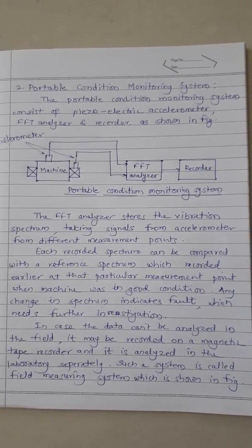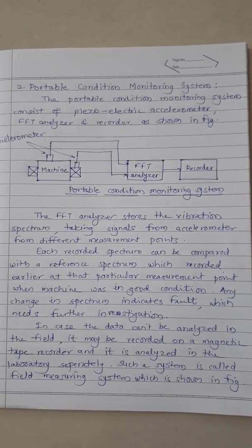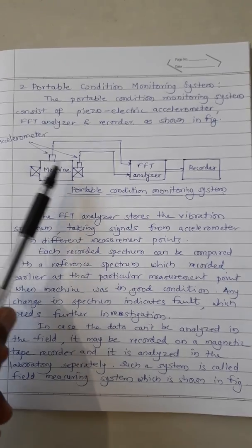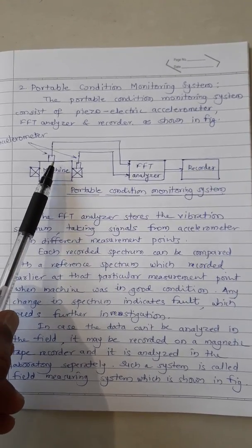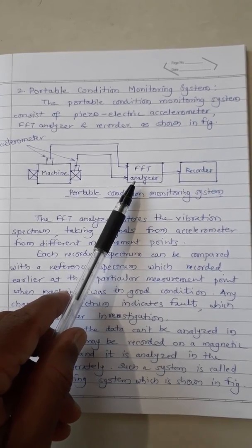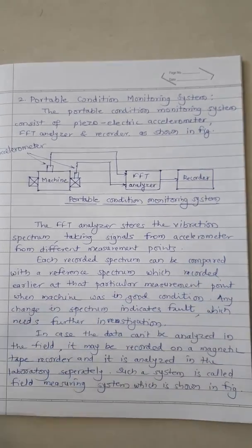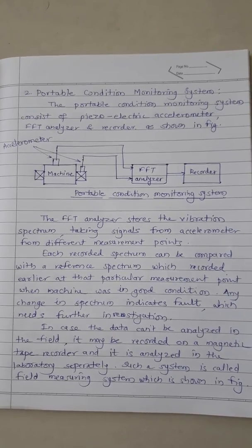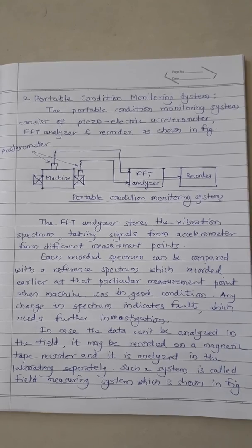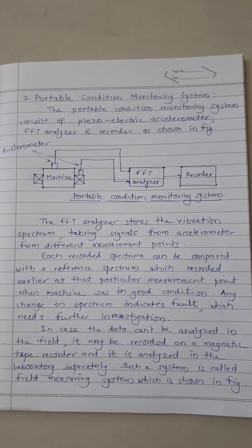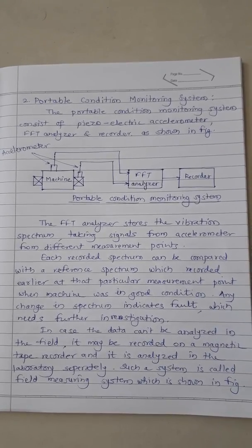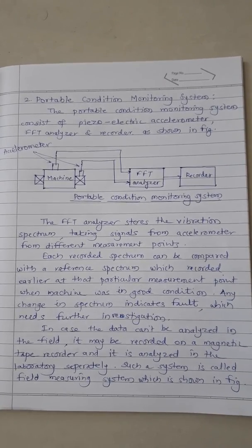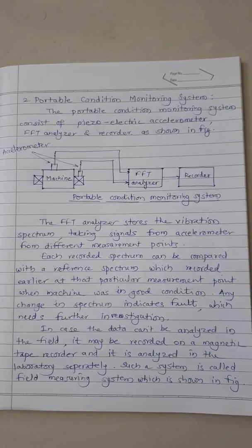The portable condition monitoring system consists of a piezoelectric accelerometer, FFT analyzer, and recorder. The FFT analyzer stores the vibration spectrum taking signals from the accelerometer from different measurement points. Each recorded spectrum can be compared with a reference spectrum recorded earlier at that particular measurement point when the machine was in good condition. Any change in spectrum indicates a fault which needs further investigation. In case the data cannot be analyzed in the field, it may be recorded on a magnetic tape recorder and analyzed in the laboratory separately.